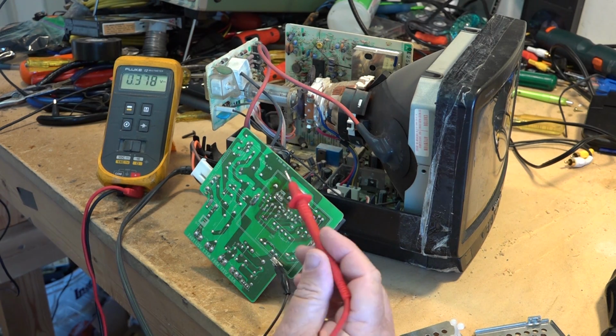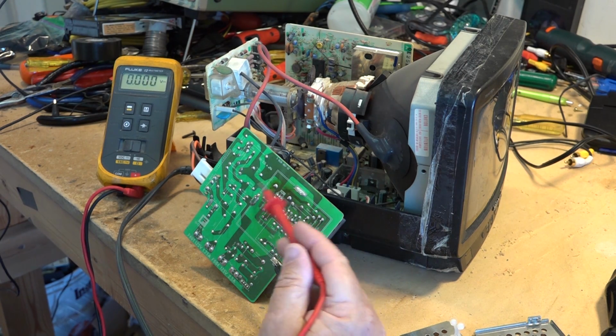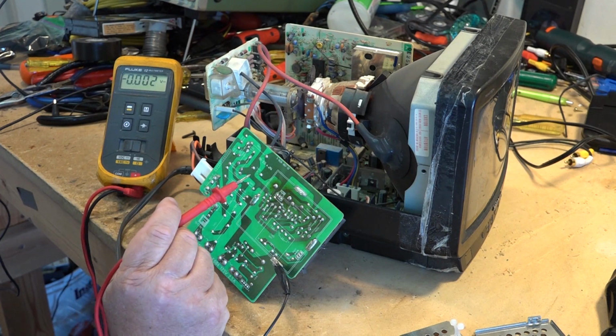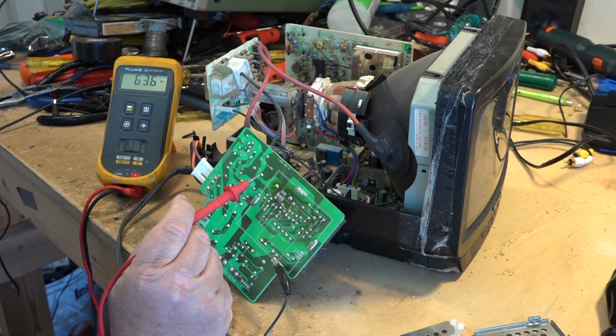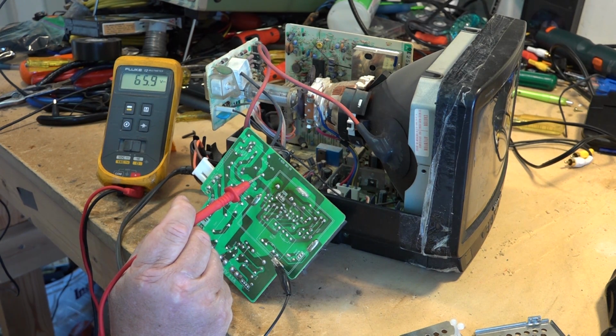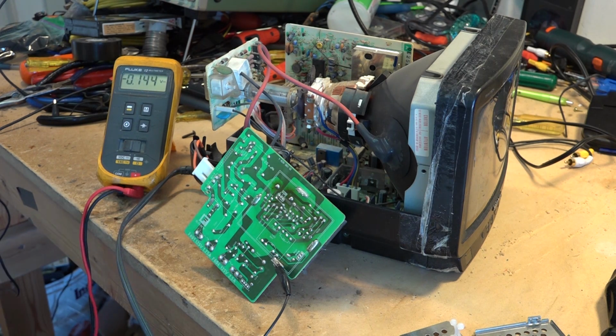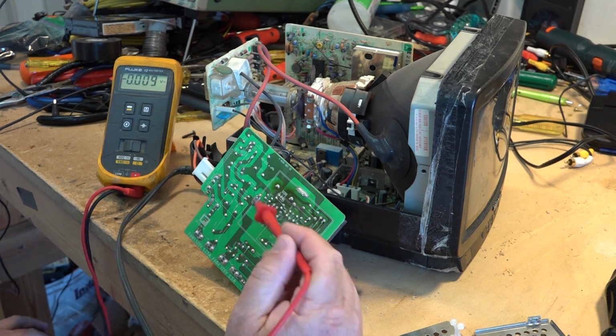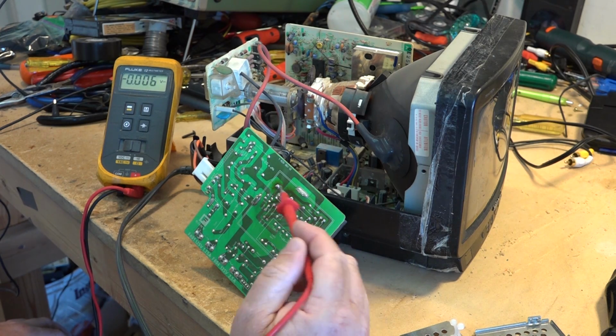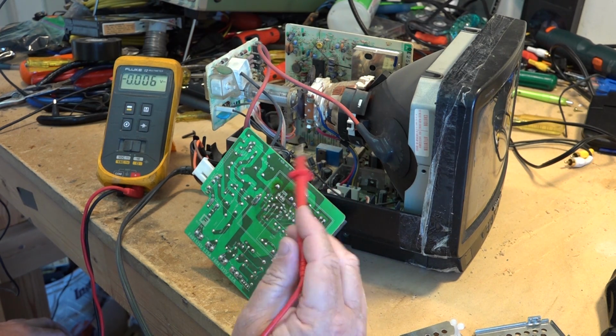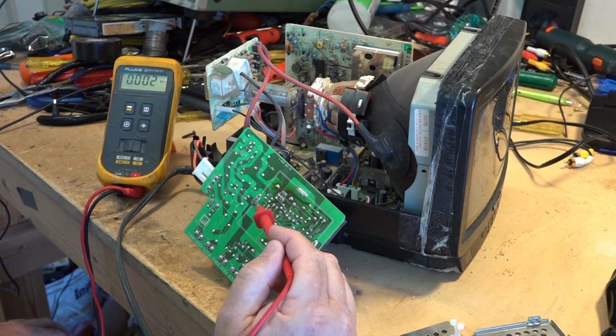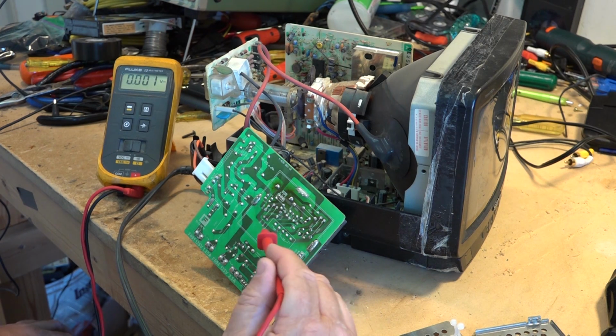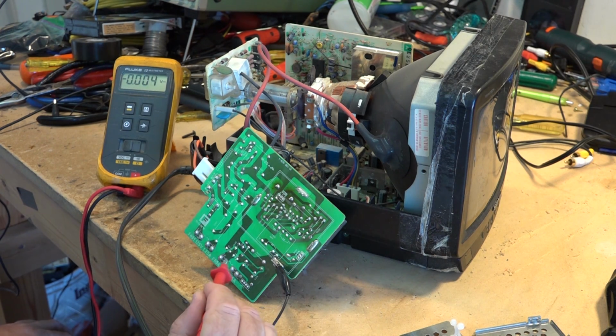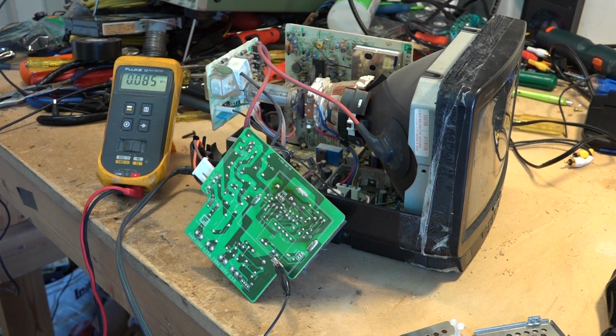This is a DC to DC converter. We're taking the 165 volts DC from the primary side. If I measure it to hot, it'll show me 65 volts, and if I measure it to the hot ground, it'll show about minus 65 volts because it's floating, right? What goes on in here is there's an oscillator that runs, switching that 165 volts on and off at a fast rate, going through the transformer, through the diode, and down to my DC side for my 20 volt supply for the TV.